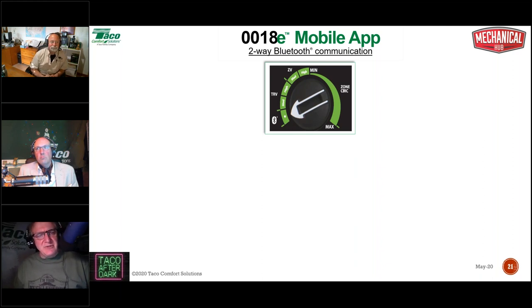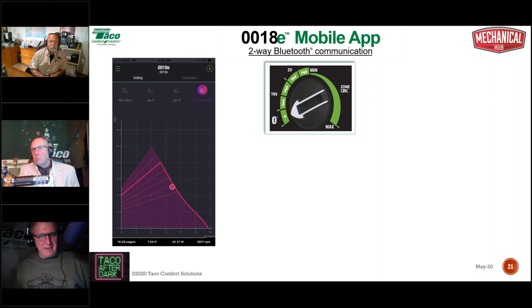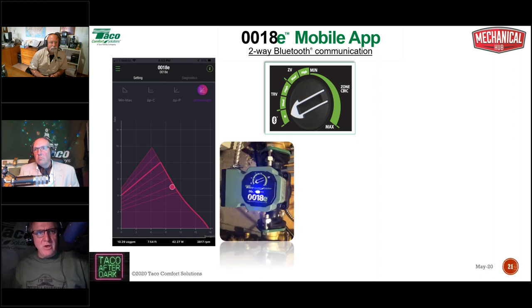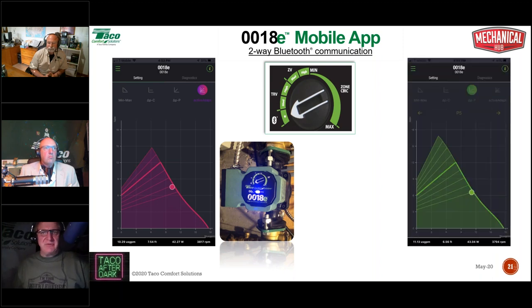And what it does now is it gives us four different operating modes. Operating mode number one is what we call active adapt, and we'll discuss that in great detail. Then you have your standard constant pressure setting, just like we have on the dial, but instead of two constant pressure lines to choose from, we have nine. You're showing proportional. Yes, that's what I meant to say, proportional pressure lines to choose from.